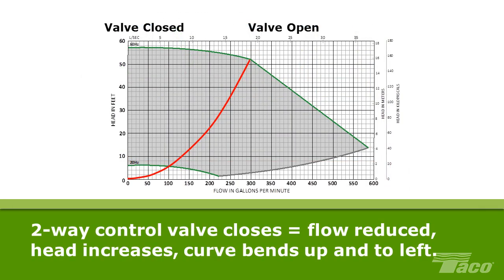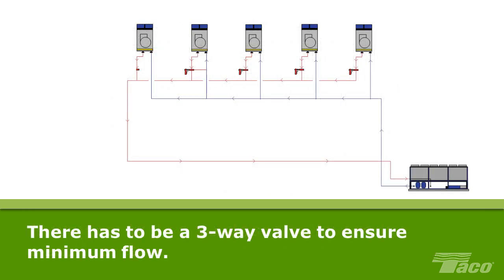As the individual two-way control valves close, flow is reduced, head pressure increases, and the system curve bends up and to the left. Note there has to be a three-way valve or bypass valve in the system to ensure that there will be minimum flow.